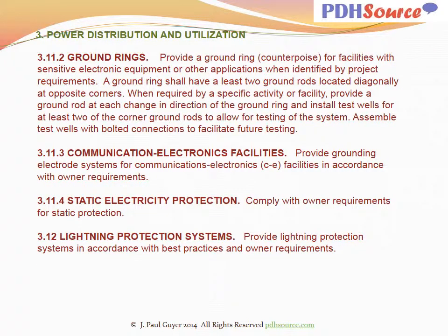Provide a ground ring counterpoise for facilities with sensitive electronic equipment or other applications when identified by project requirements. A ground ring shall have at least 2 ground rods located diagonally at opposite corners. When required by a specific activity or facility, provide a ground rod at each change in direction of the ground ring and install test wells for at least 2 of the corner ground rods to allow for testing of the system. Assemble test wells with bolted connections to facilitate future testing.